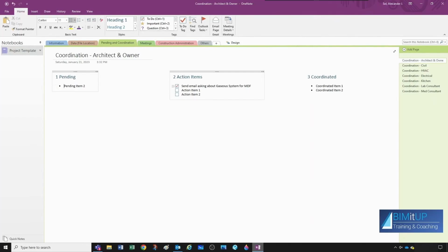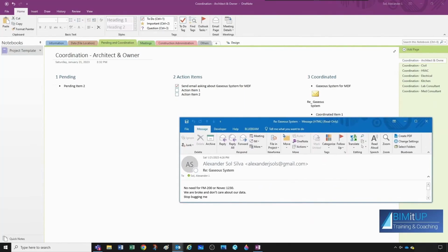But let's say I do receive a response and it's not required, then I can come here to coordinate it. And I know that there's no gaseous system required for that MDF. So I'm gonna just place it here. And the beauty of this is that I have the email that directed me not to provide that. So I can simply just drag and drop it here. I attach the file and I can simply cut it and paste it right under my item. And then now I have this as a coordinated item. So if they ever ask, well, why didn't you provide a gaseous system? I can simply double click here. I open the attachment. So I have it right here from the horse's mouth. No need for FM 200 or Novec 1230.